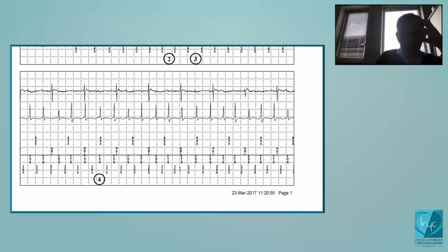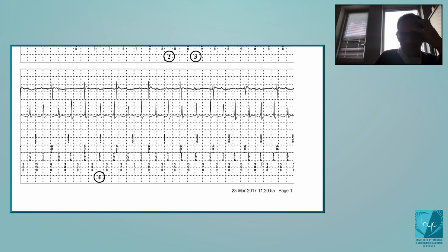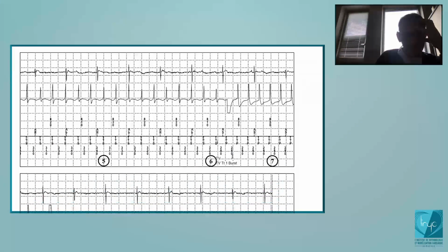At one time, there is a stabilization of the rhythm. You see here, still a VS, VS, and then here there is a stabilization, 1, 2, 2, 2, 2, 2 consecutive cycles, and after X consecutive cycles, you will detect and deliver.